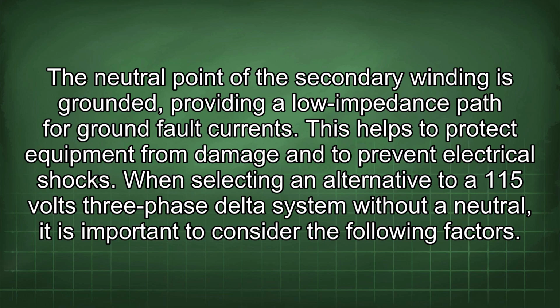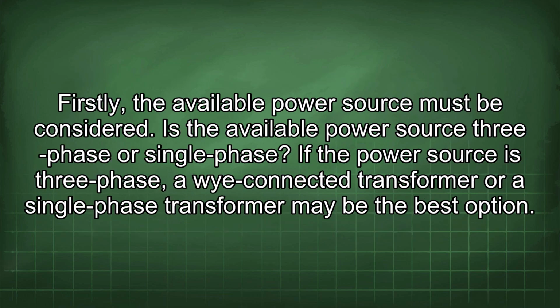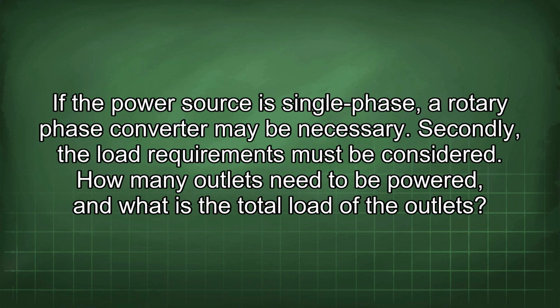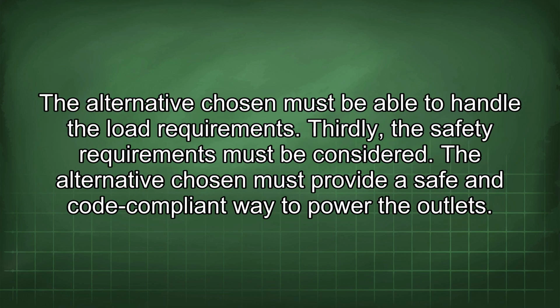When selecting an alternative to a 115 volts three-phase delta system without a neutral, it is important to consider the following factors. Firstly, the available power source must be considered. Is the available power source three-phase or single-phase? If the power source is three-phase, a Y-connected transformer or a single-phase transformer may be the best option. If the power source is single-phase, a rotary phase converter may be necessary. Secondly, the load requirements must be considered. How many outlets need to be powered, and what is the total load of the outlets? The alternative chosen must be able to handle the load requirements.